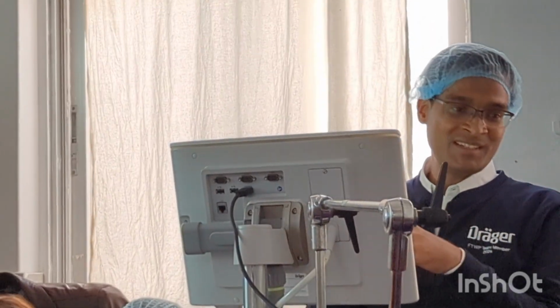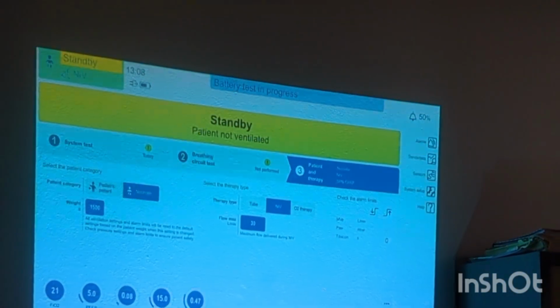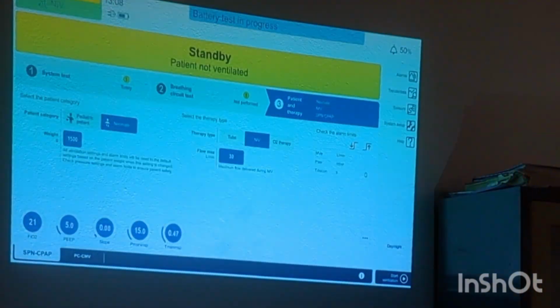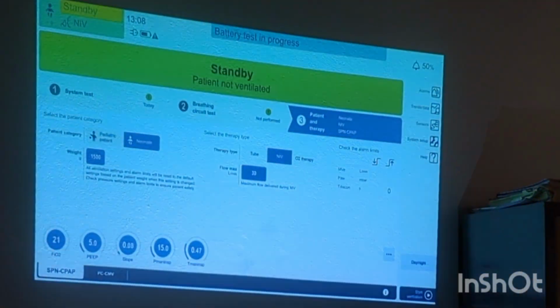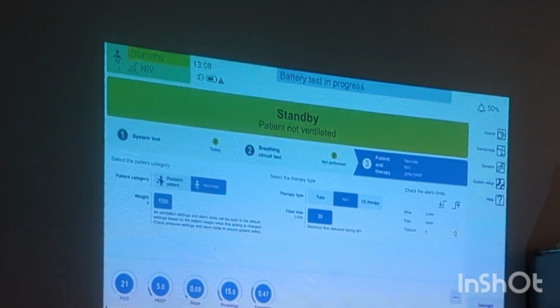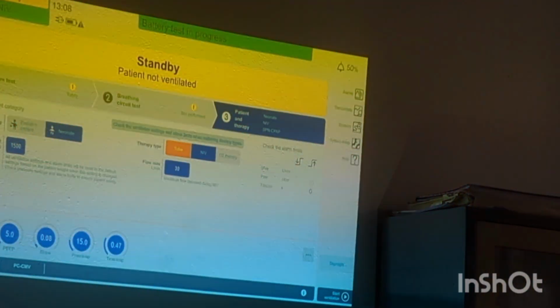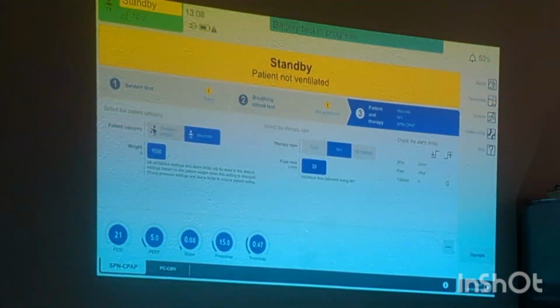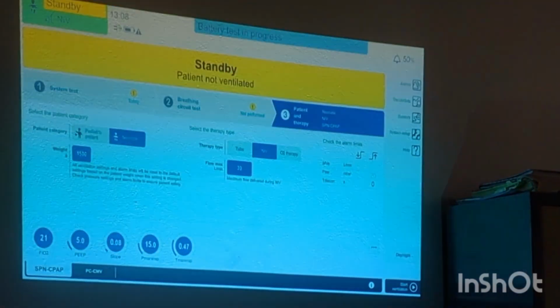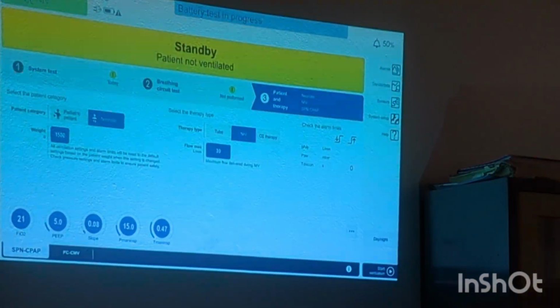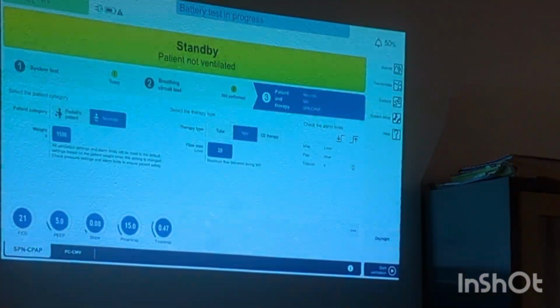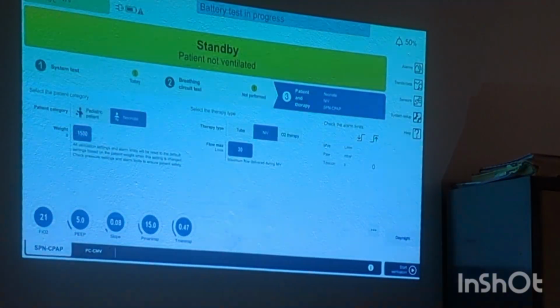So there is no point in giving all these messages which are not real. That's the reason they have not given it, and really they use only nasal IMV. In most ventilators, the low air pressure alarm will not come, because this resistance will always create a certain pressure. You can see the graph, but you have to look at the patient parameters at that time.